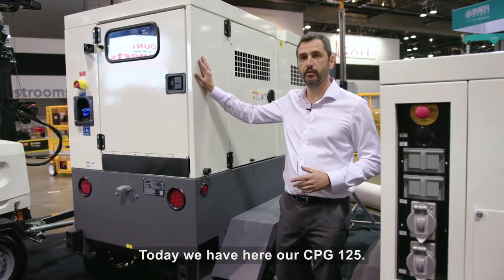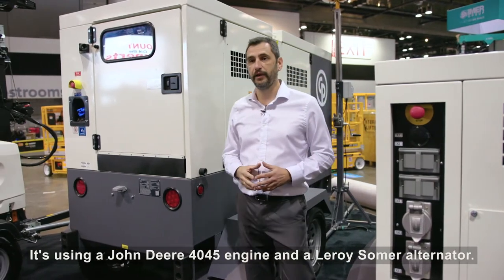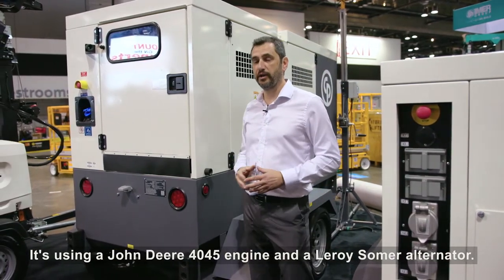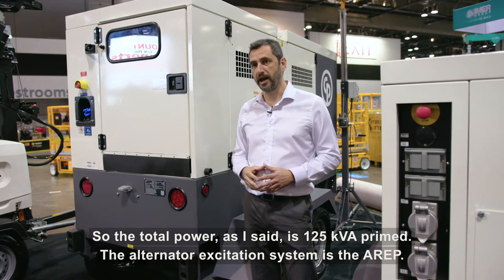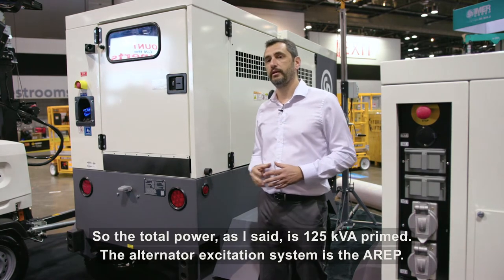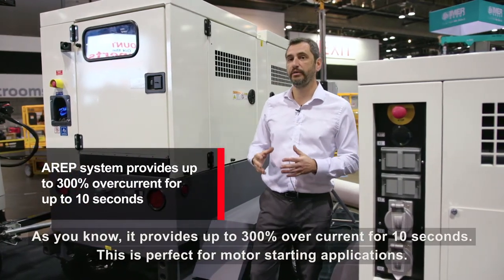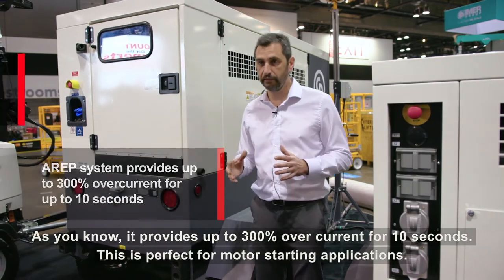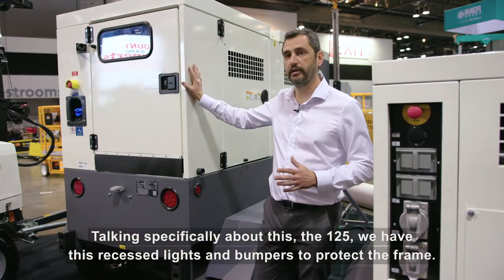Today we have here our CPG 125. It's using a John Deere 4045 engine and a Leroy Somer alternator. The total power is 125 KVA prime. The alternator excitation system is the AREP, which provides up to 300% over-current for 10 seconds. This is perfect for motor starting applications.